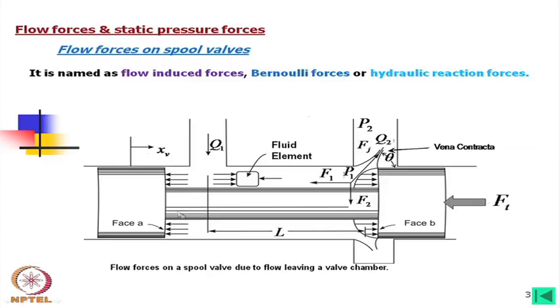Another important parameter is the length L, measured from the middle of the orifice. If the stroke is xv, this distance is xv/2, and L is the damping length. Knowing the valve geometry, we can calculate L. Pressure p1 is measured inside; p2 is outside the orifice. From section 1 to inside, the pressure is approximately p1, since there is very little restriction.